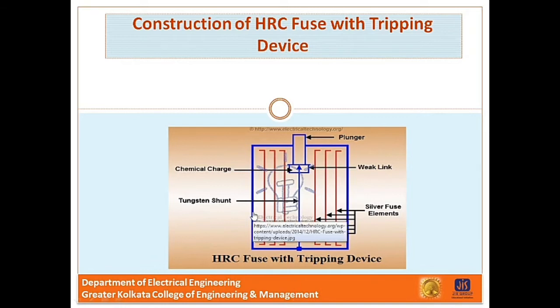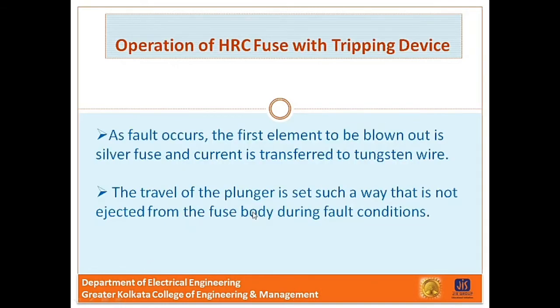Okay. Now what is the operation of HRC fuse with tripping device? When a fault occurs, the silver fuse elements are first to be blown out and then the current is transferred to the tungsten wire. Now the weak link in series with the tungsten wire gets fused and causes the chemical charge to be detonated. This forces the plunger outward to operate the circuit breaker. The travel of plunger is so set that it is not ejected from the fuse body under fault condition.